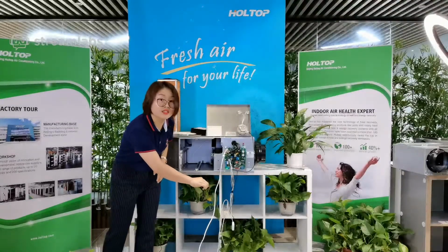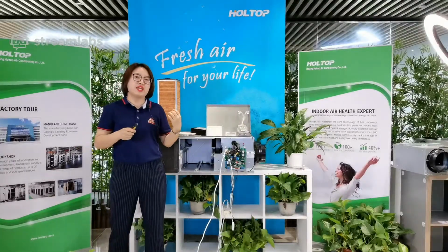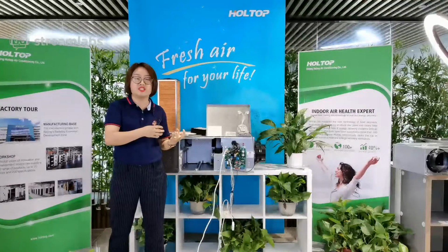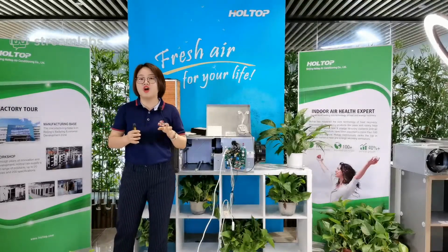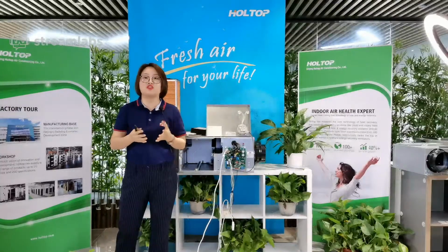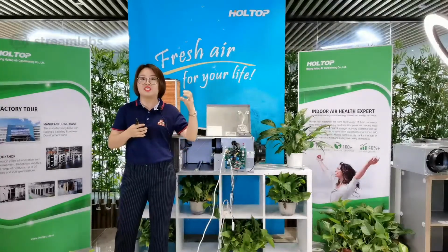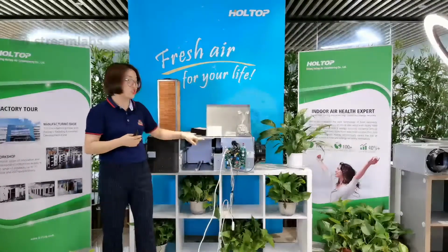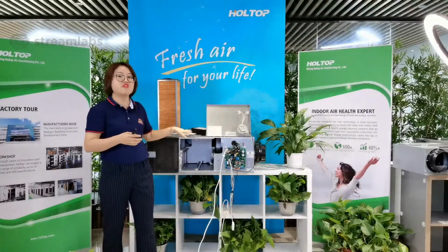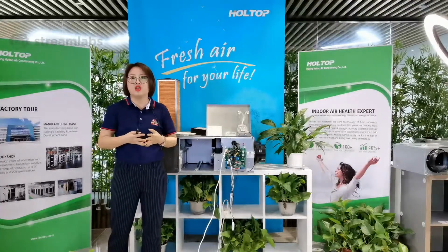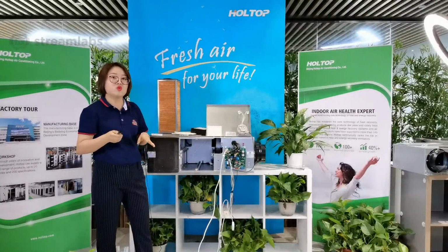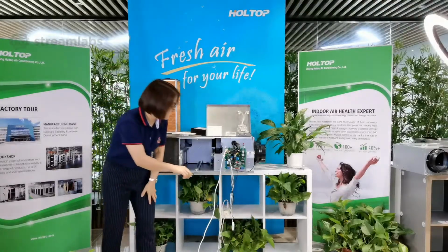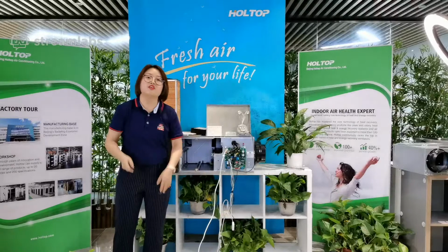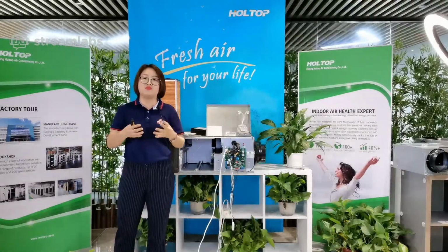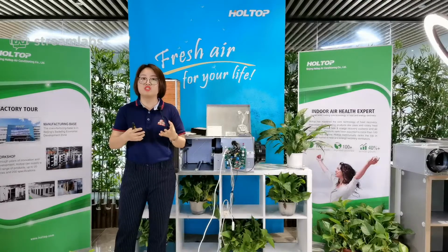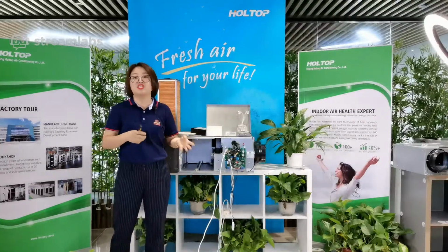This one, can you see that? Yes. It can connect with the external switch connector. So this connector is like an on and off switch for this ERV unit. Once the external device, like the air conditioner, is on and makes the external switch closed, the ERV unit will automatically start. What's more, it has a built-in RS485 connector here. This one. If a project has a BMS system, you can use the BMS system to control the ventilator as well.